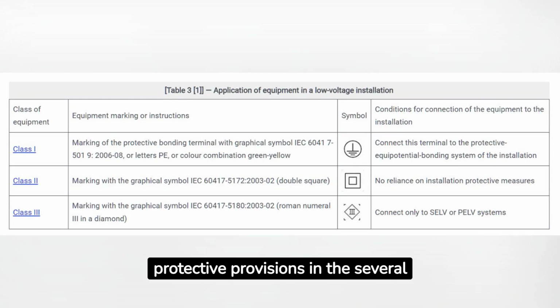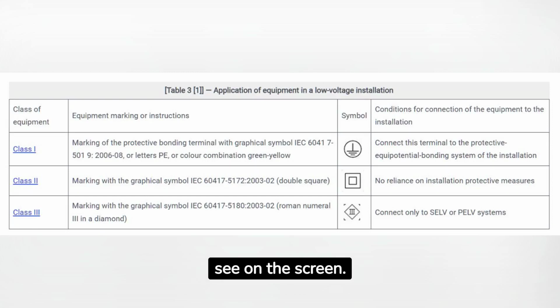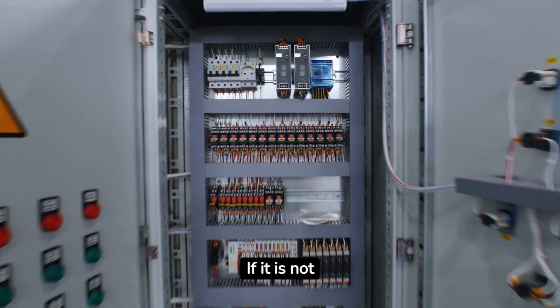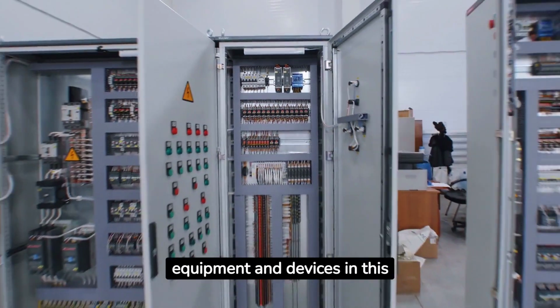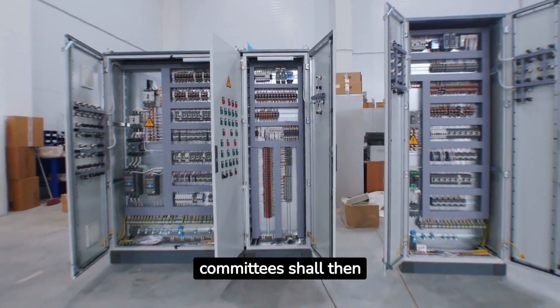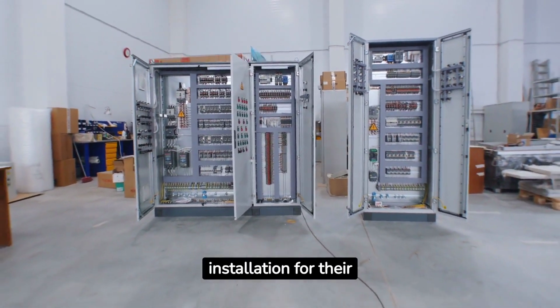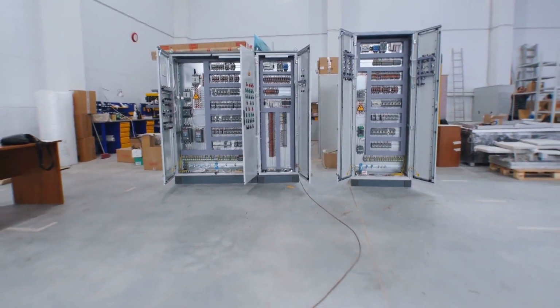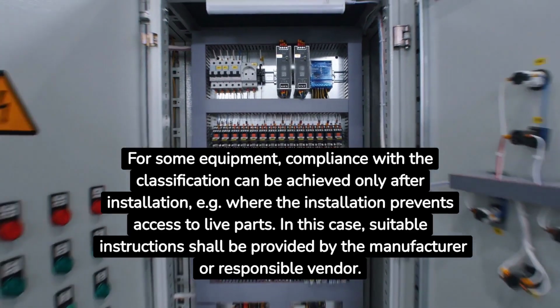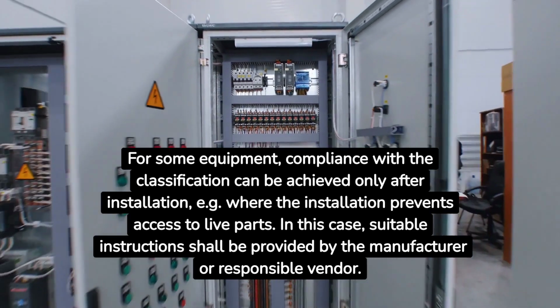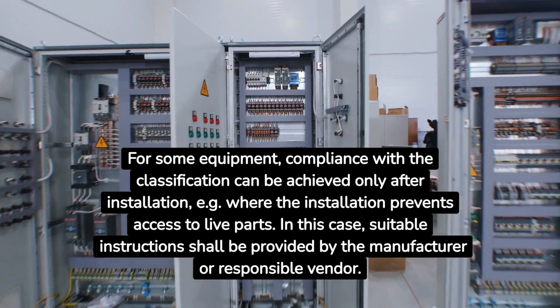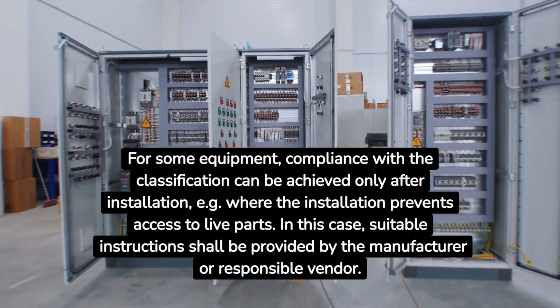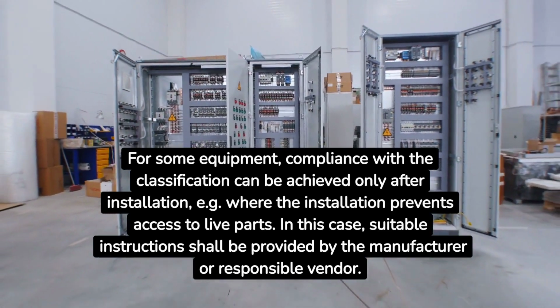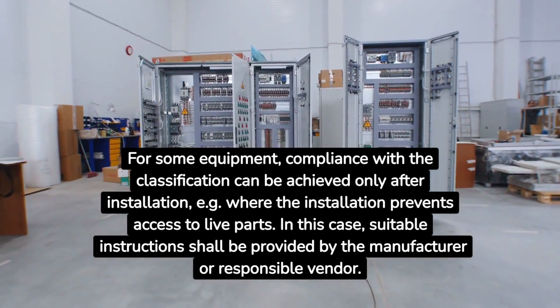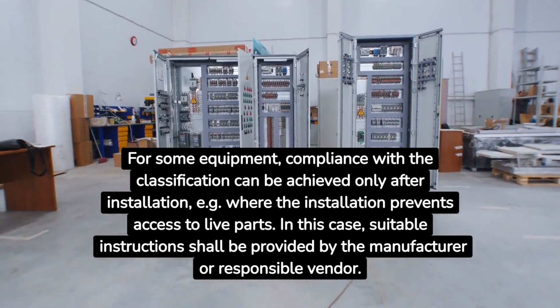The use of protective provisions in the several classes of equipment is described in the table you see on the screen. If it is not appropriate to classify equipment and devices in this way, technical committees shall then specify the relevant methods of installation for their products. For some equipment, compliance with the classification can be achieved only after installation, e.g., where the installation prevents access to live parts. In this case, suitable instructions shall be provided by the manufacturer or responsible vendor.